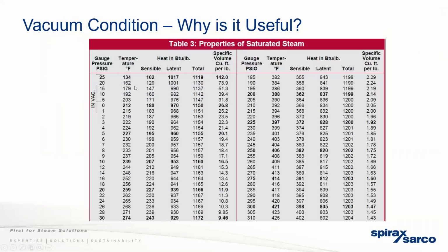One other thing from the steam table I forgot to bring up is the condensate temperature. At 20 inches of vacuum, we have a condensate temperature of 160 F. So you're really pulling all that energy out. There's going to be no flash losses in the condensate return system.